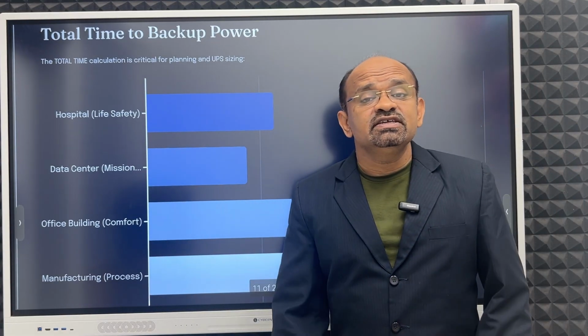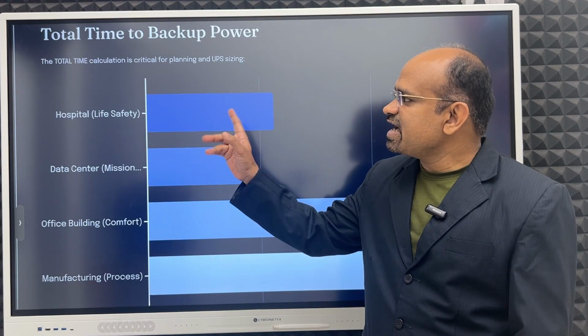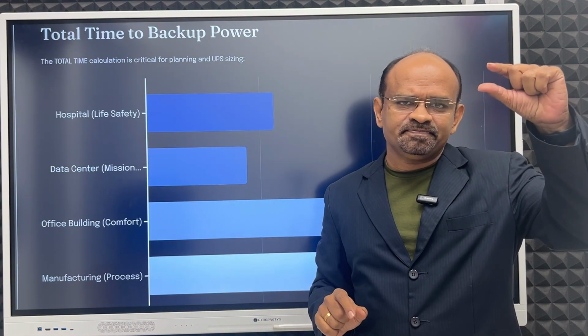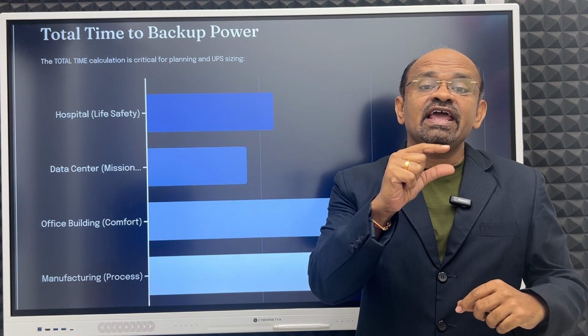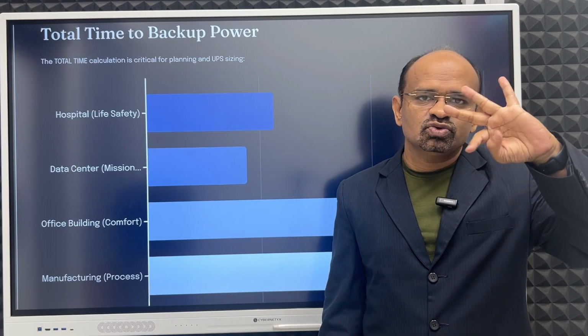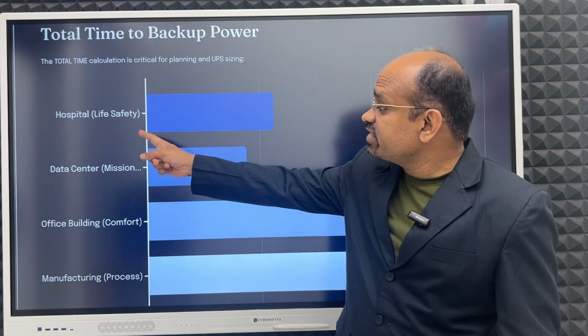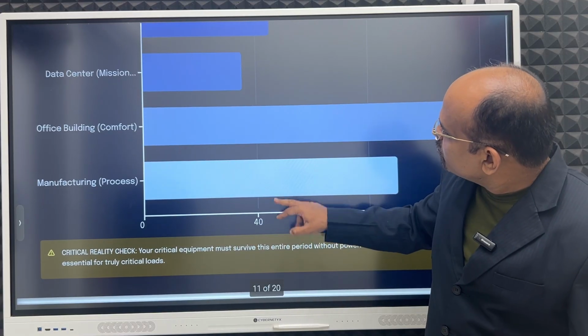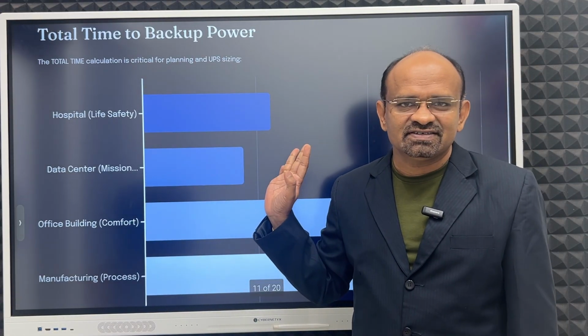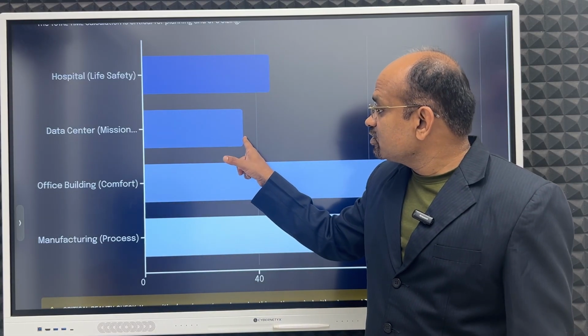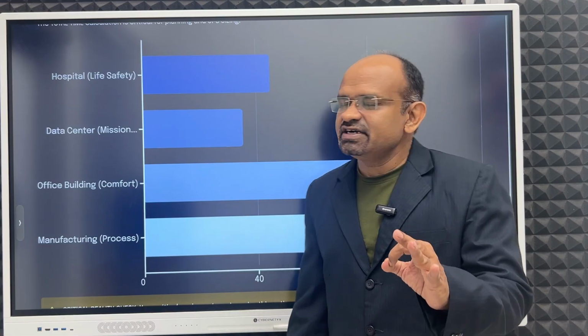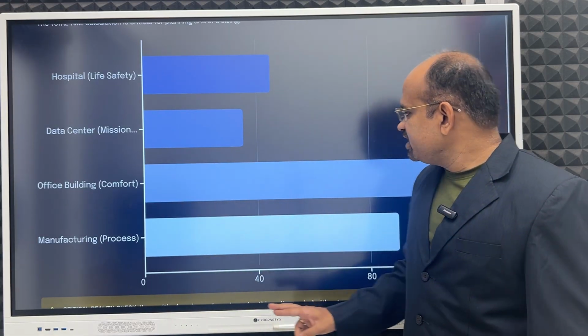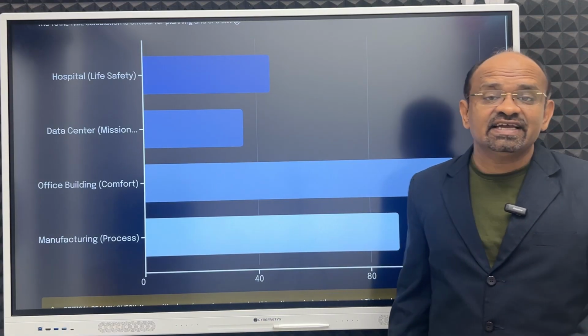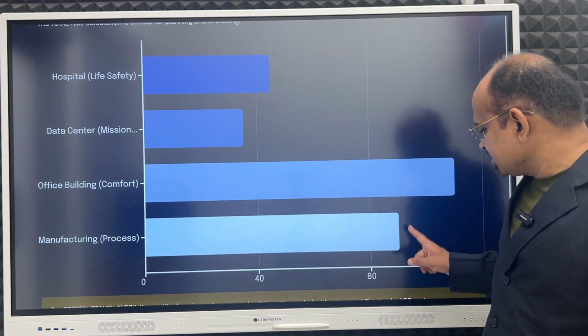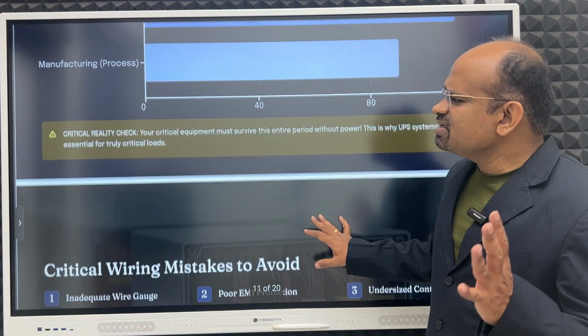Now you will ask me, how much should the backup time be? Industry wise, I have shown you the time. Sensing, confirmation, then delay for engine warm up, and then delay for load. All these three things cumulatively should take how much? 45 to 50 seconds for hospitals, let's say 50 seconds. For data centers, it is 35 seconds, even within 30 seconds. Office buildings can take up to 110 seconds, and manufacturing processes can take 90 seconds in total. This is just the benchmarking I have given to you.